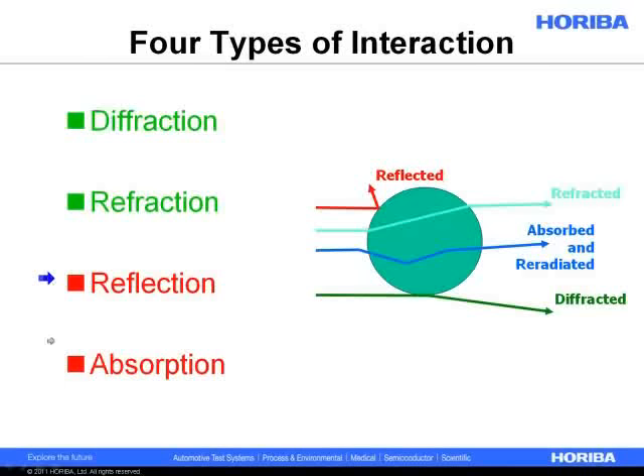The Mie scattering theory gives us an imaginary component of the refractive index that we can use to help correct for these poor light interactions. Absorption is also not good because the light is basically entering the particle or being absorbed at the surface. Worst case, it's re-emitted through fluorescence or phosphorescence; usually it gets re-radiated as infrared heat. If you're running paint pigments or carbon black, you're hitting it with light that's absorbed and re-radiated as heat. So we like diffraction and refraction; reflection and absorption work against us, but we have tools to correct for them.